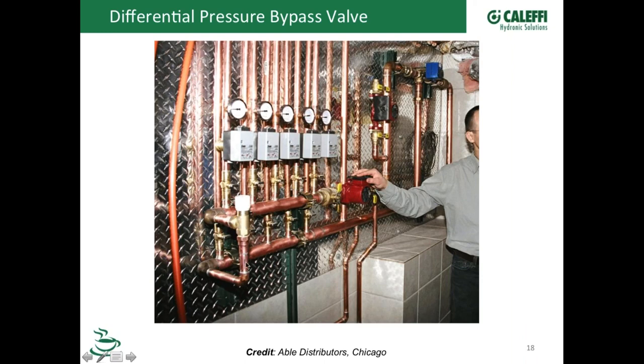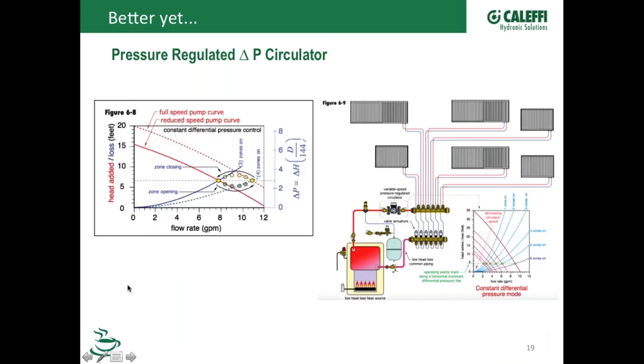One other thing I'll add that you kind of jogged my memory. I've had guys say, we put these in and then we go to purge out these zones and we're having a hard time getting a good purge through there. It's a good idea to put a ball valve in here, because if you're going to do a fast fill, or some guys fill with a garden hose to purge their system, it can blow right through there and not get a good flow going through them. So some guys will put a ball valve right here, anywhere there, that you can actually shut that off 100% from the circuit. So if you're going to do a high pressure fast purge with a purge cart, for example, if you're pumping glycol into the system with a purge cart, you could be blowing that valve open. It's going to make it hard to purge those zones possibly.